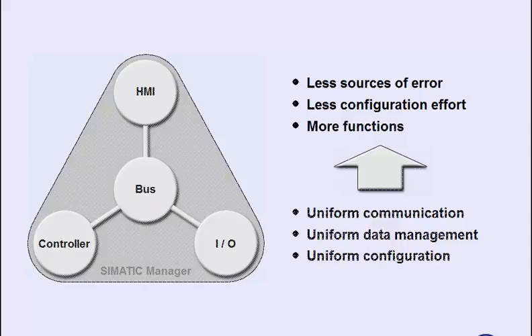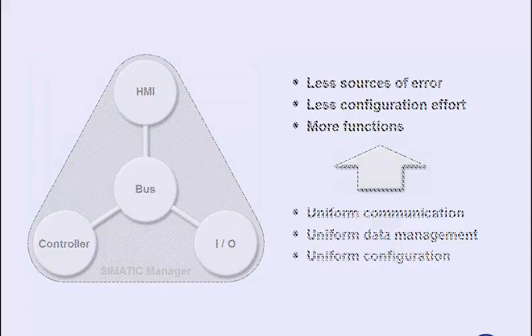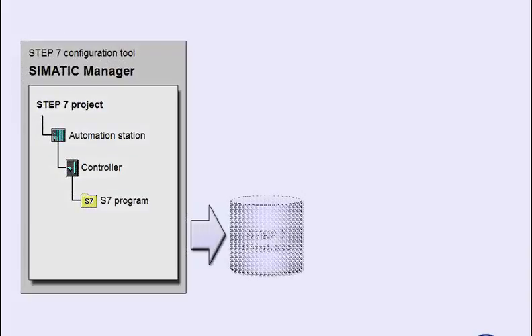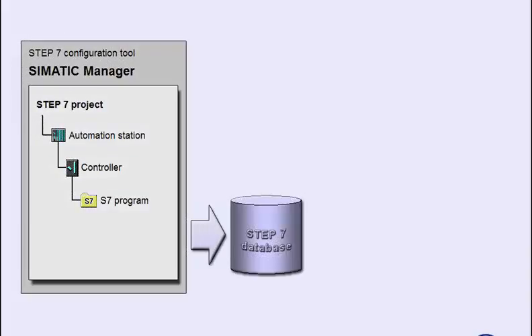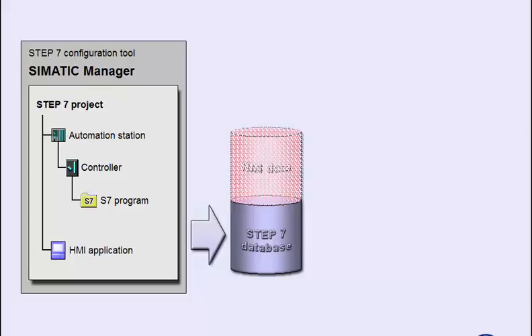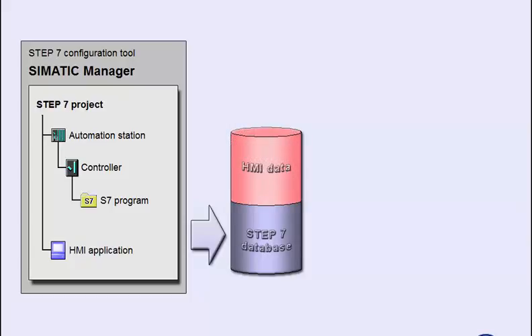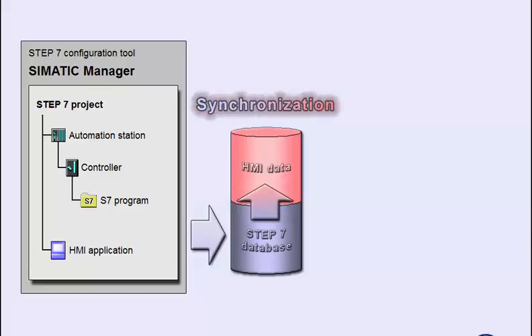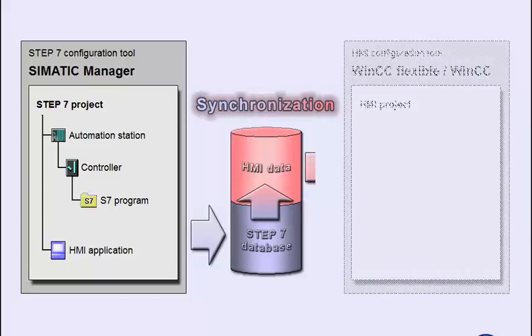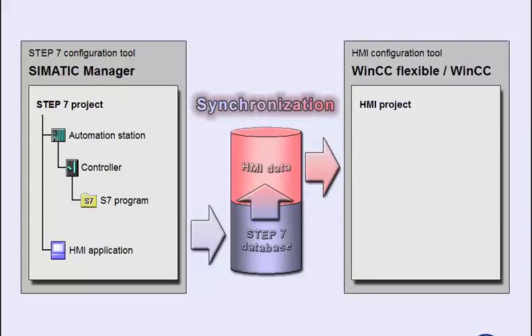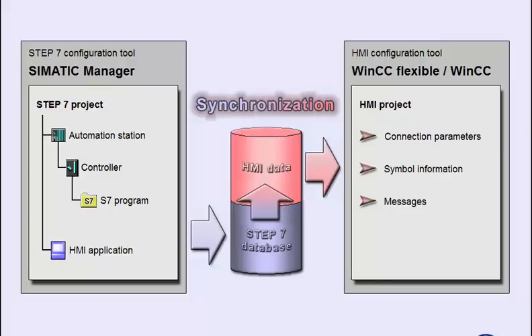The Step 7 configuration is stored by the SIMATIC Manager in a common database. When an HMI application is integrated, either a WinCC Flexible or a WinCC Project is created that references the Step 7 project. All relevant parameters are taken from the Step 7 database. When the HMI project is now further edited with the appropriate configuration tool, the connection parameters, symbol information, and messages are ready for use as a basis.